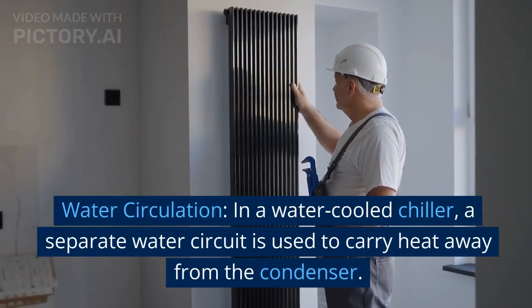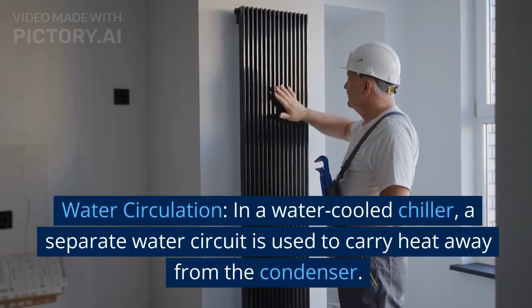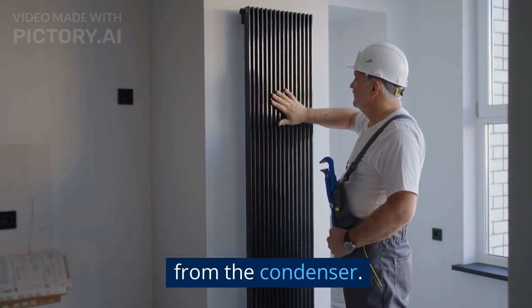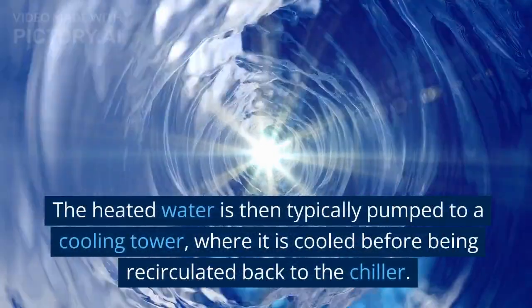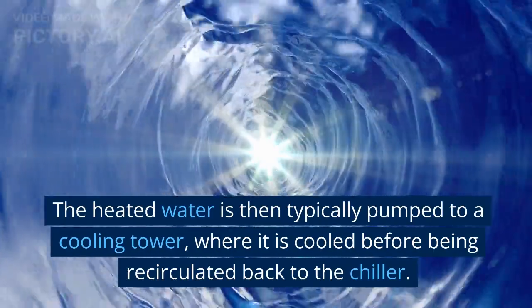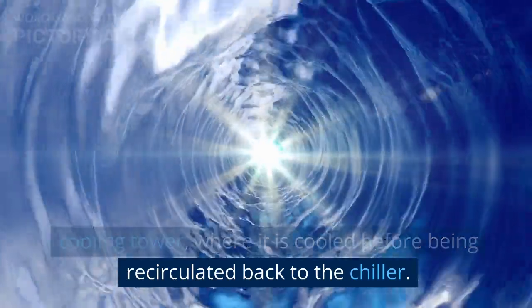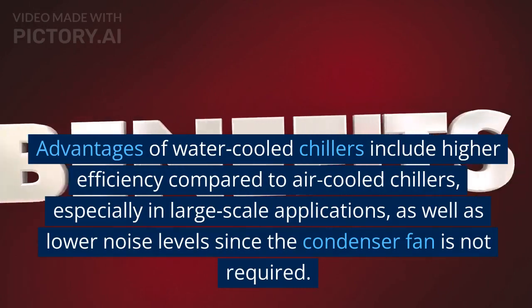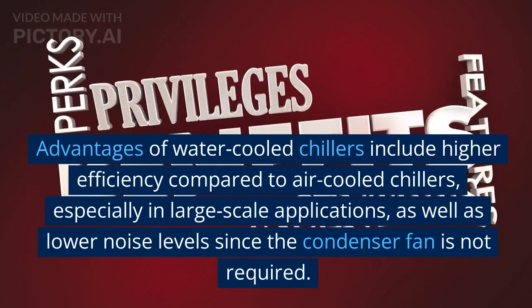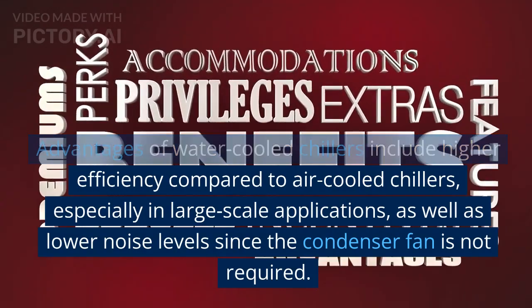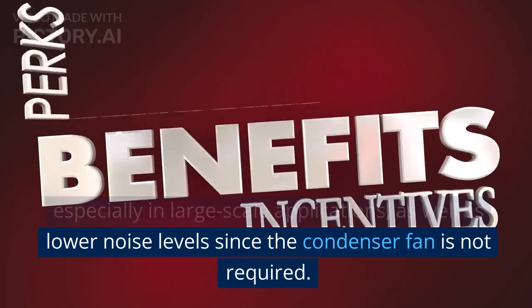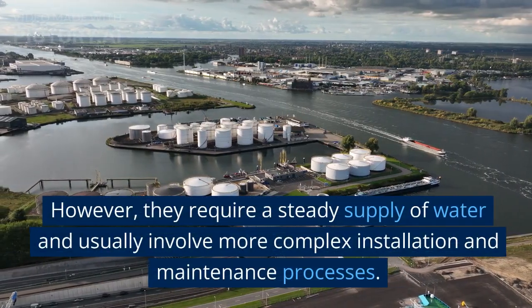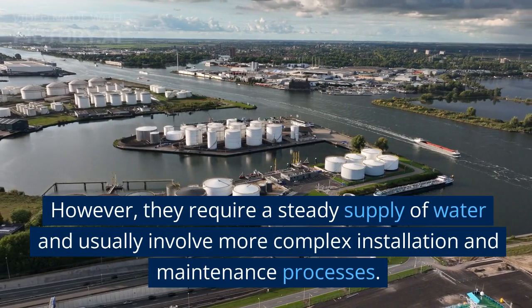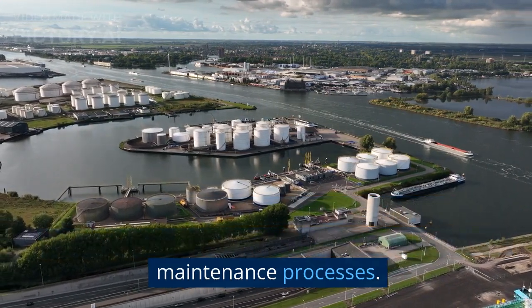Water circulation. In a water-cooled chiller, a separate water circuit is used to carry heat away from the condenser. The heated water is then typically pumped to a cooling tower, where it is cooled before being recirculated back to the chiller. Advantages of water-cooled chillers include higher efficiency compared to air-cooled chillers, especially in large-scale applications, as well as lower noise levels since the condenser fan is not required. However, they require a steady supply of water and usually involve more complex installation and maintenance processes.